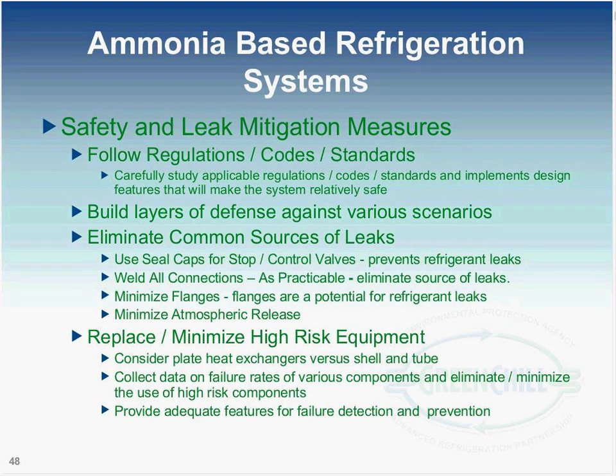And when you are designing it, select the equipment very carefully, and eliminate or minimize the high-risk equipment, such as, consider using plate exchangers. As Scott has mentioned, it is a highly reliable device versus shell and tube. Write down the failure rates of the components that you are going to use and minimize the use of components that possess high risk, such as, for example, the gauges, a very high failure rate. Flexible hoses, they have a very high failure rate. Take it out. Minimize it.